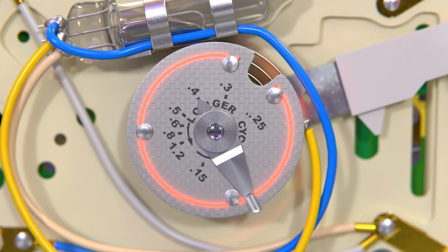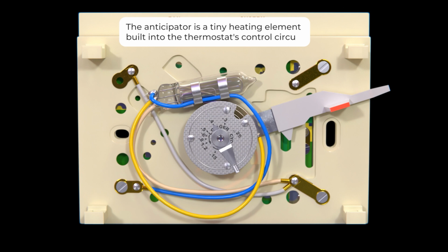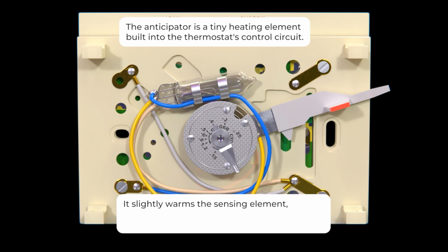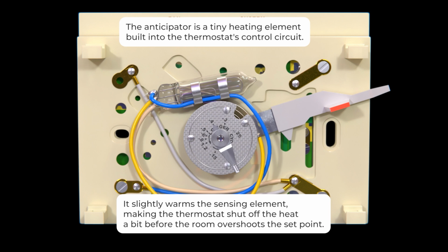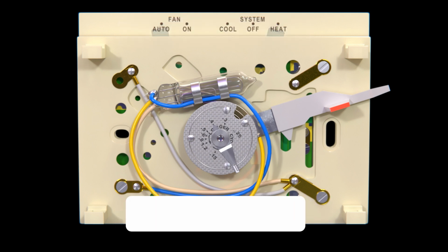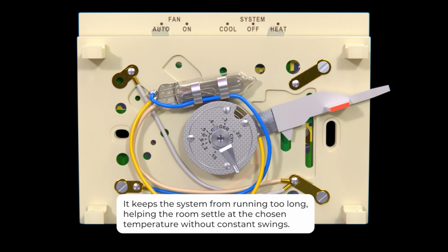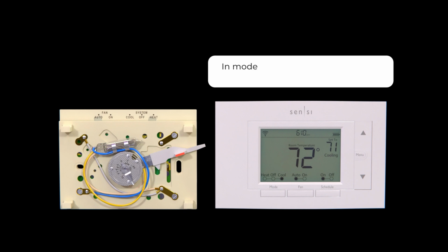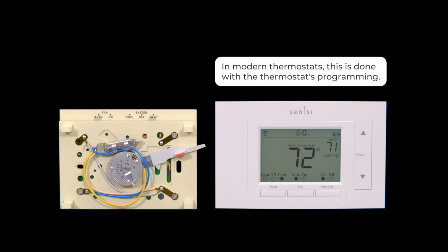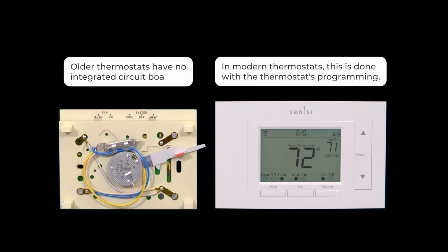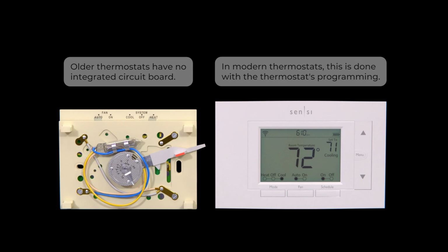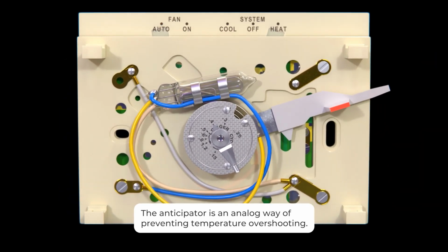The anticipator is a tiny heating element built into the thermostat's control circuit. Its job is to slightly warm the thermostat sensing element, making it shut off the heat a bit before the room overshoots the set point. By doing this, it keeps the system from running too long, helping the room settle right at the chosen temperature without constant swings. In modern thermostats, this is done through the thermostat programming.